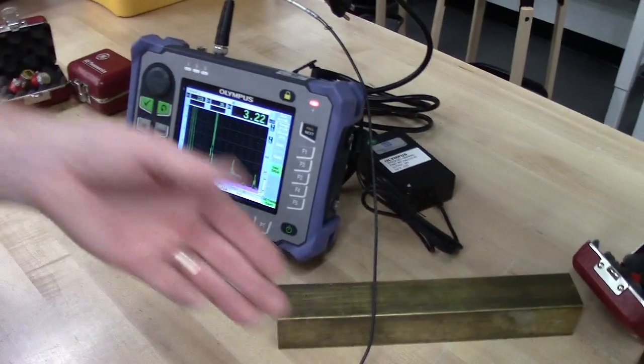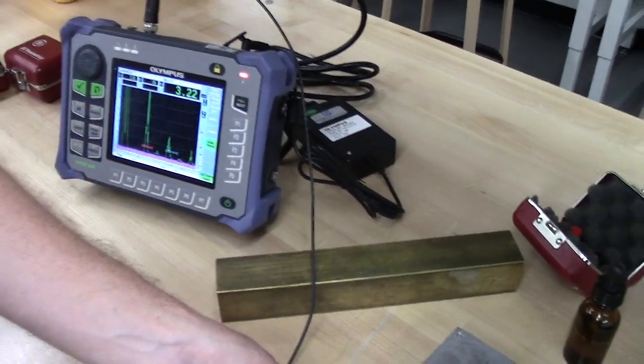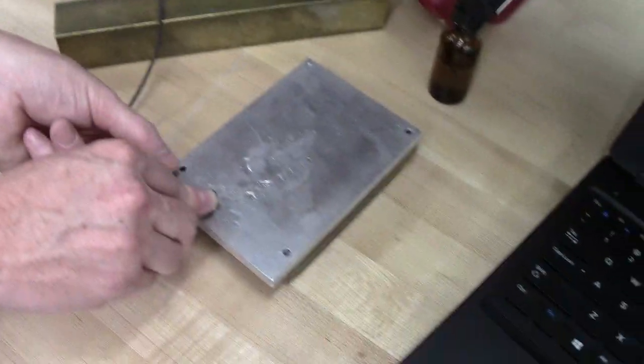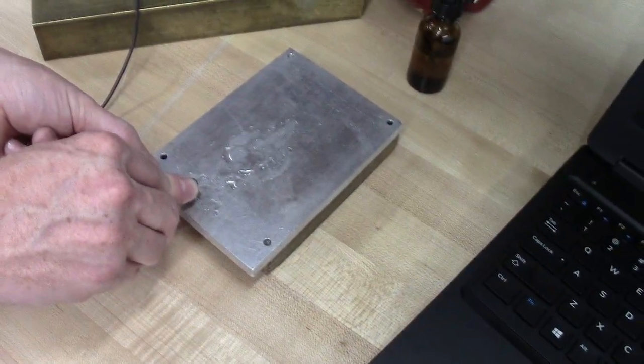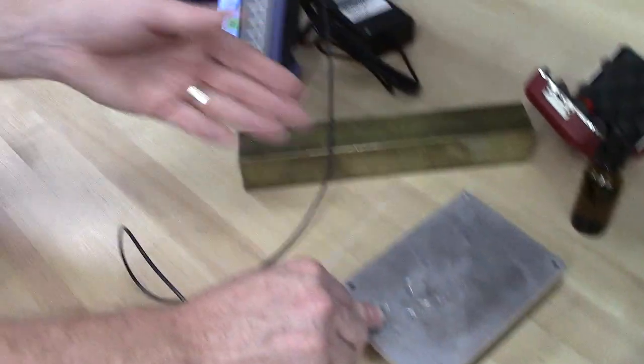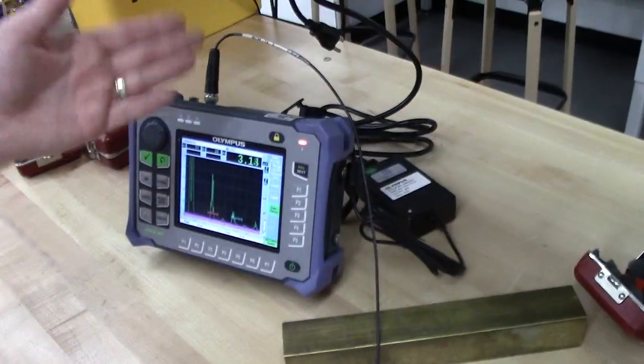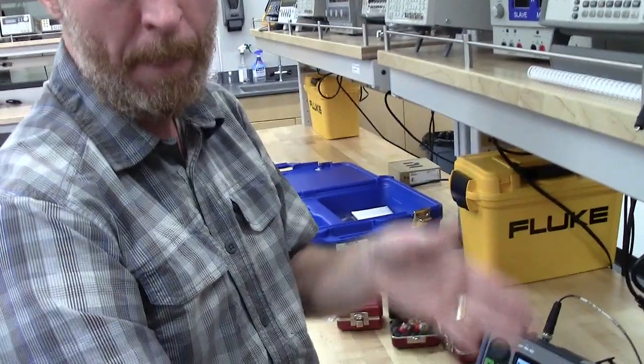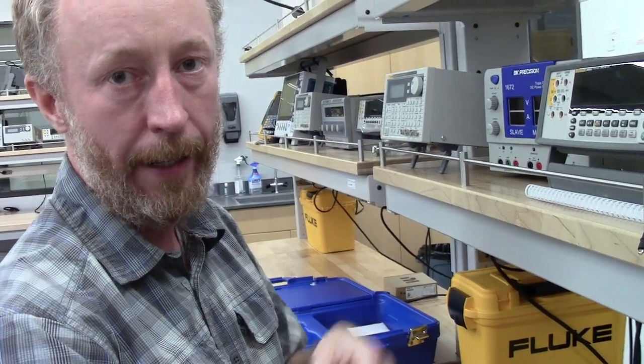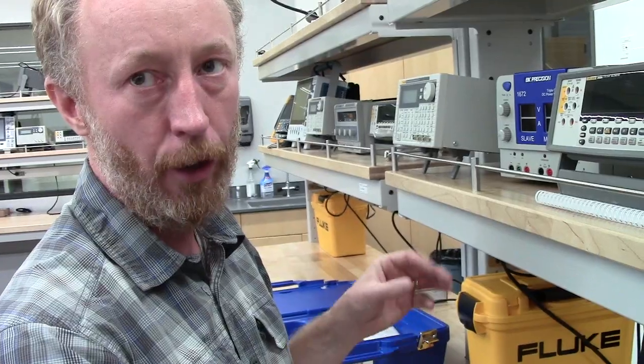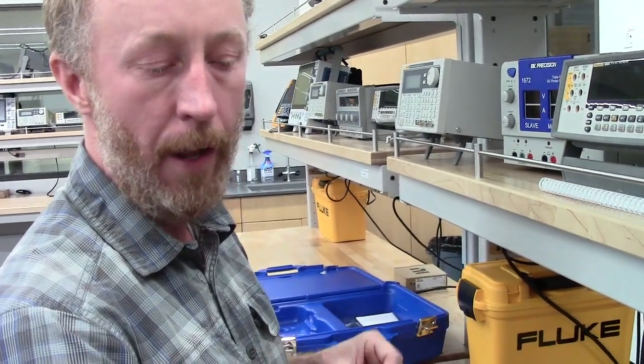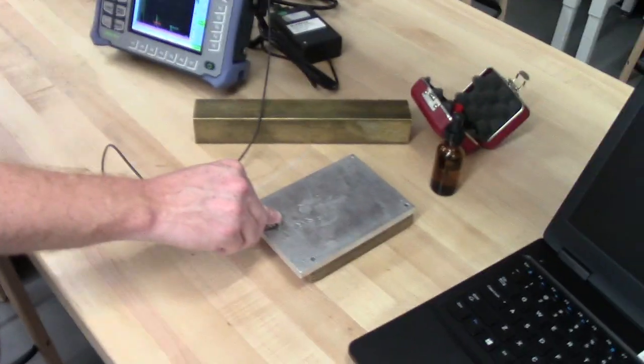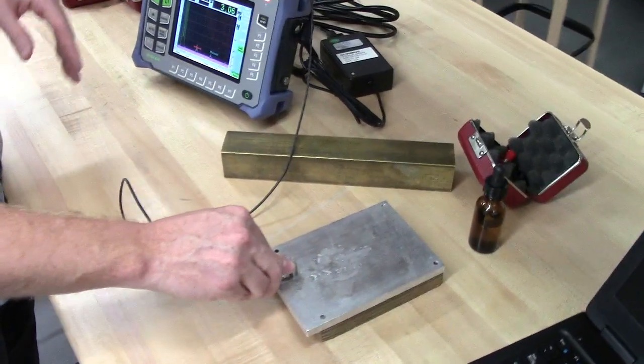You want to do that simple calculation. Take some calipers. Measure the known thickness. You do this to measure the time through it. And then divide the distance by the time. And you'll get the speed. And then go to something like Engineering Toolbox online and look at the longitudinal wave speed for aluminum. And make sure that you're in the ballpark.